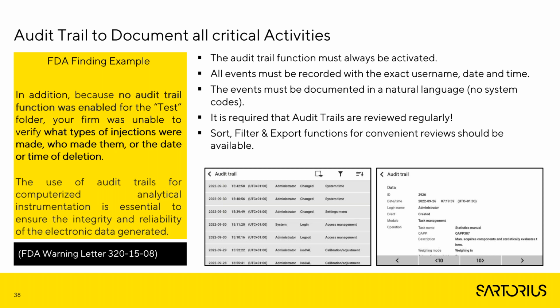The audit trail must also be simple to read and comprehend because it will be often examined for irregularities. Since it is easier to review it on a PC rather than on the instrument because of the huge amount of data, you should have the option to export the audit trail file for external analysis. Of course, sorting and filtering options may also be quite useful for locating specific audit trail data, and all this is available on the Cubis II balance. Next slide, please.